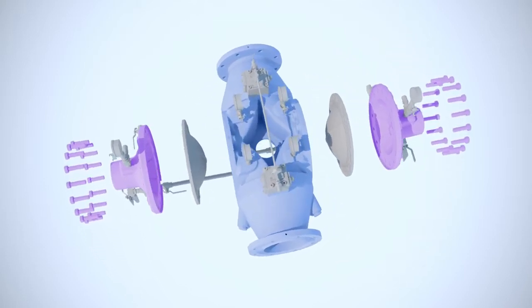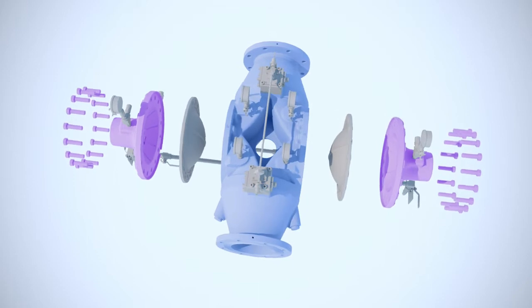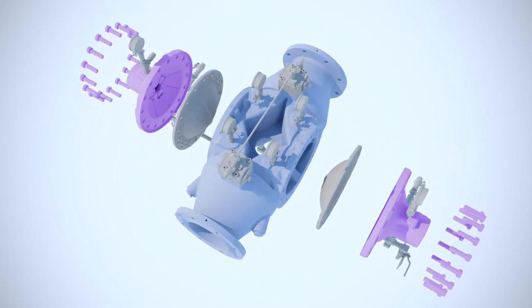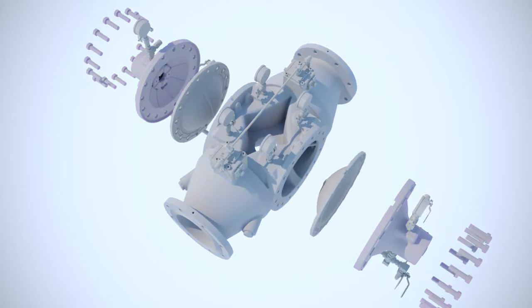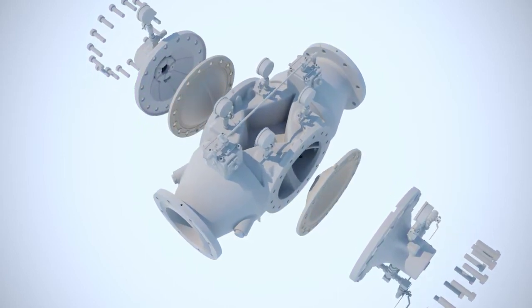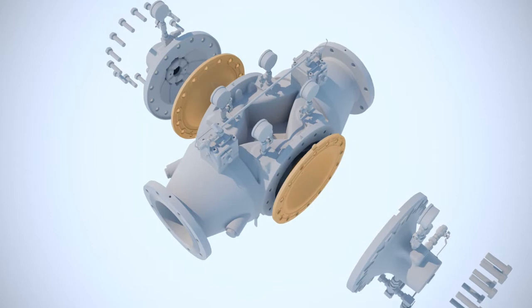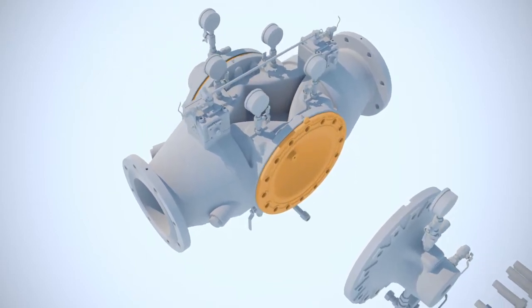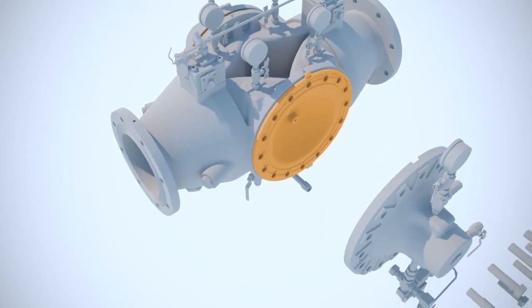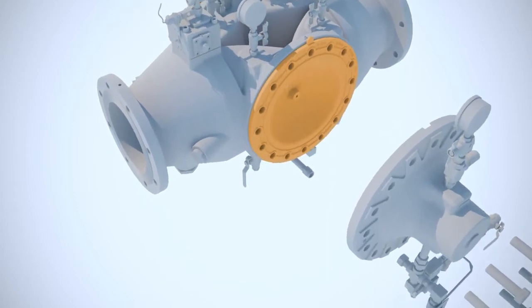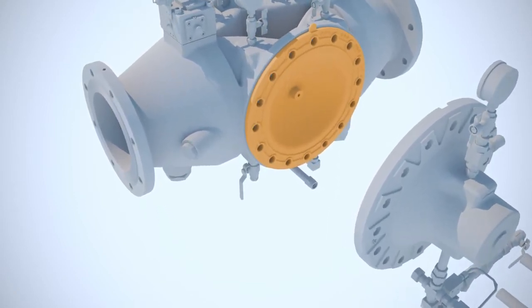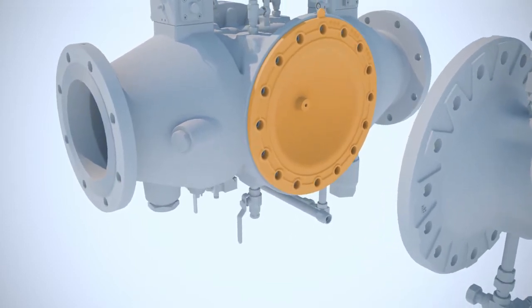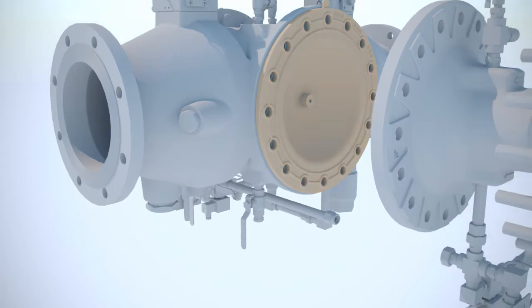The VDD deluge valve is a fully elastomeric deluge valve with a perfect type seal certified as class 6 according to ANSI FCI 70-2 2013 and IEC 60534-4 which is achieved using an internal diaphragm made of EPDM reinforced with nylon making it highly resistant and immune to chemical aggression caused by foam concentrates or diluted concentrates of chemicals present in industrial firefighting water.